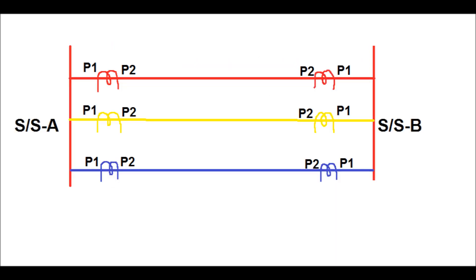The CT should be connected with proper polarity in each substation. A transmission line is connected between substation A and substation B. P1 is connected on the bus side of substation A. Similarly, P1 in substation B is connected on the bus side, and P2 should be connected on the line side, that is, towards the line direction.